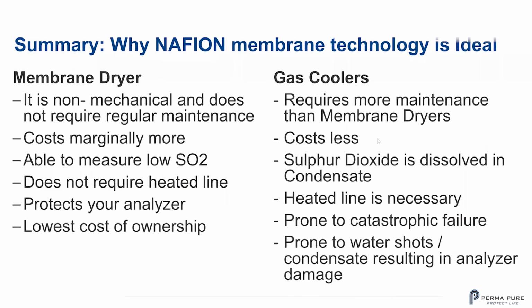So let's do a summary of why Nafion membrane technology is ideal. Number one, Nafion dryers are not mechanical and do not require regular maintenance, cost marginally more, are able to measure low SO2, do not require a heated line, protect your analyzer, and have by far the lowest cost of ownership. Gas coolers are the most common technology. They require more maintenance than membrane dryers. They cost less. SO2 is dissolved in the condensate. A heated line is necessary. They're prone to catastrophic failure and prone to water shots or condensate, resulting in analyzer damage.